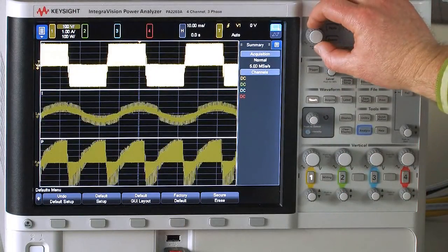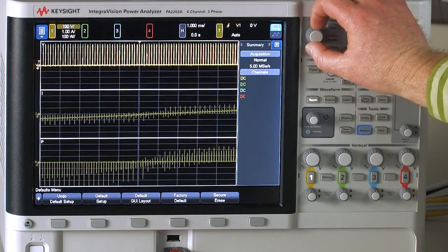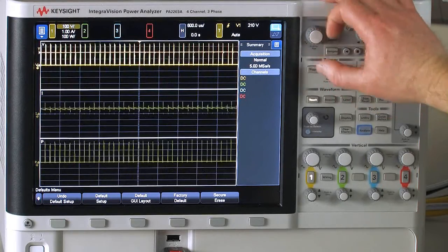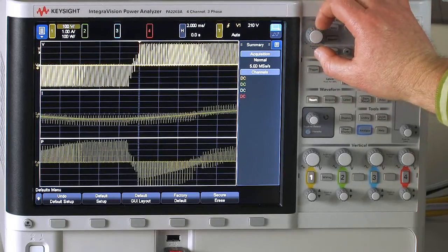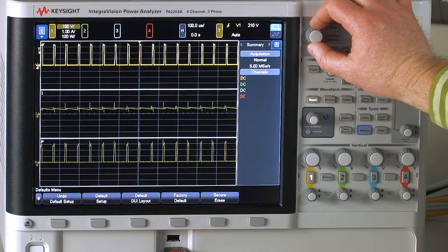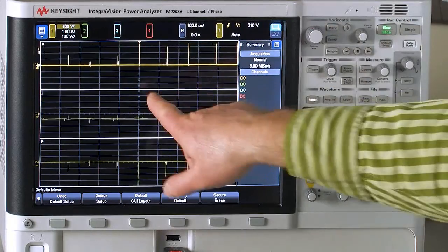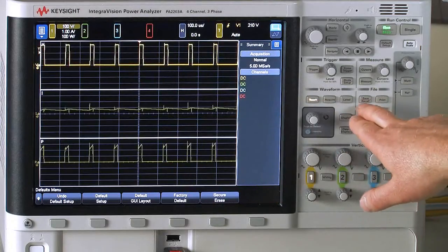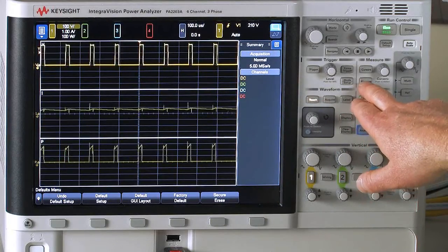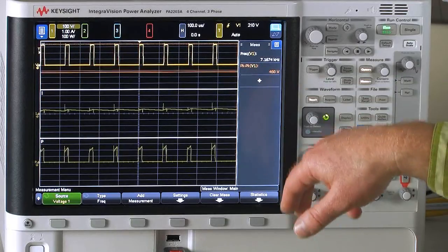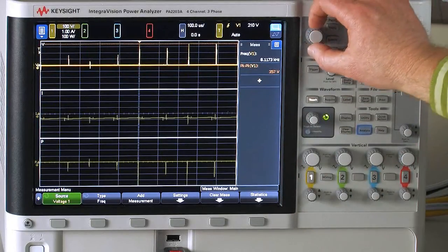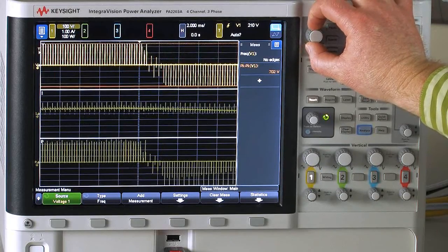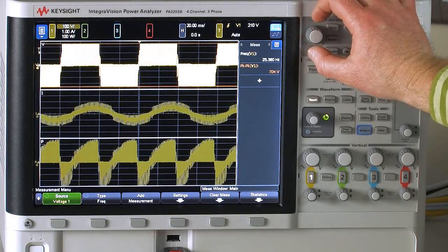So I can actually see that it's a PWM signal that's trying to generate a sine wave here, and this is just one of the three phases being driven into the motor. I can zoom in on that and see the PWMs changing pulse widths and see that it's running at about eight kilohertz. It modulates it a little bit.